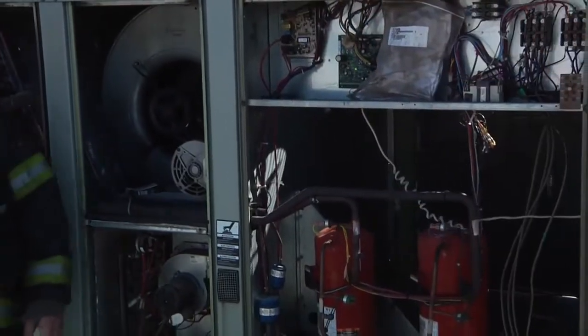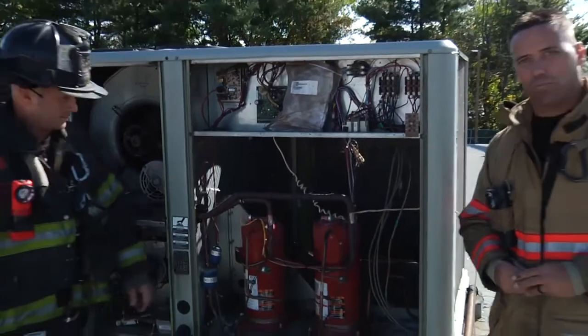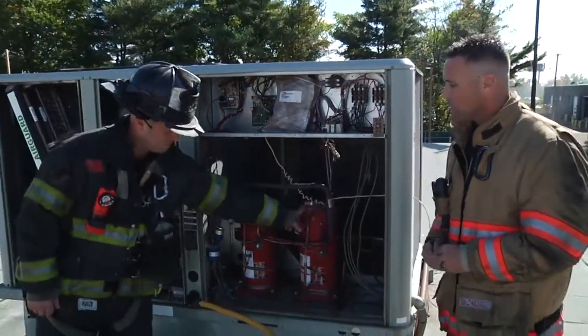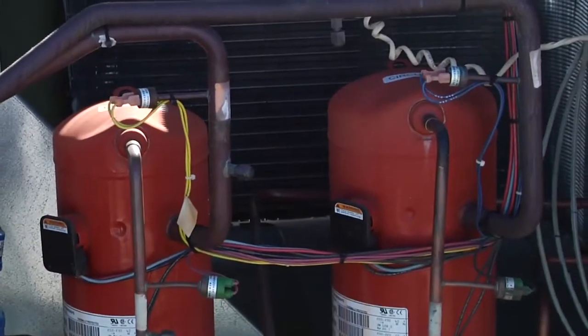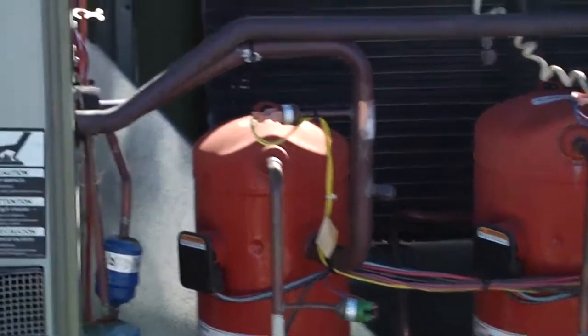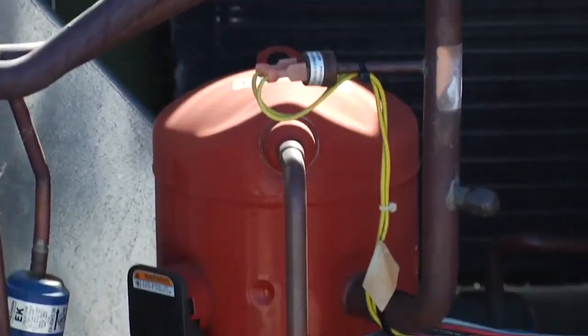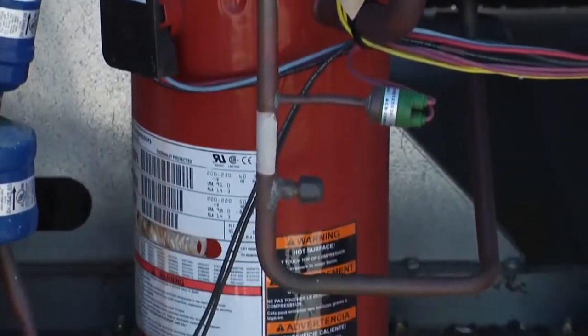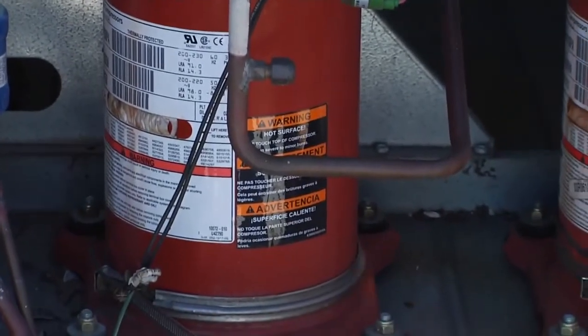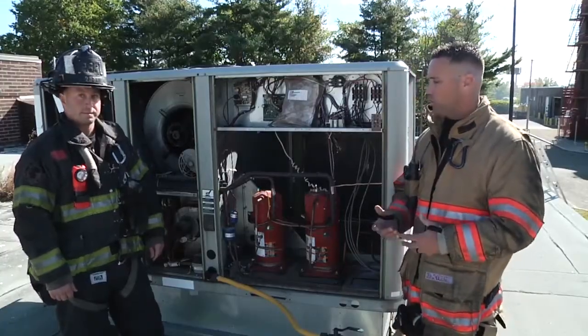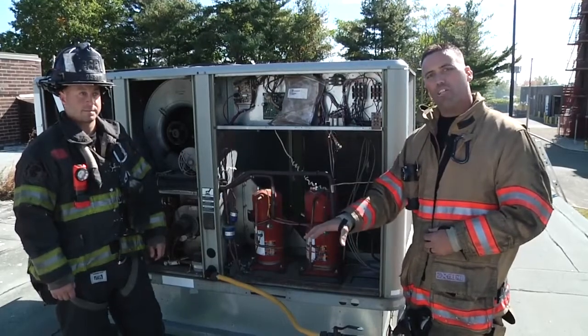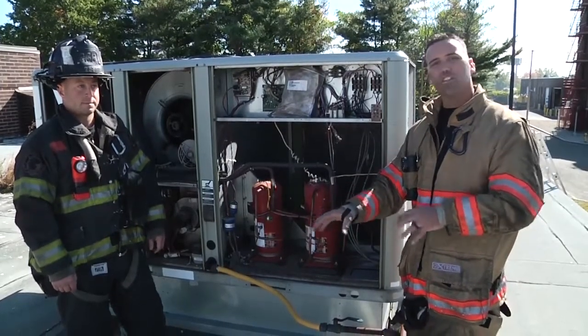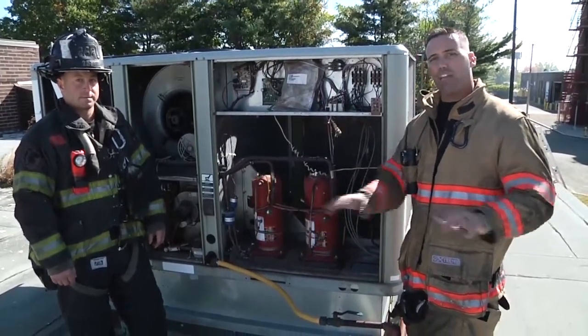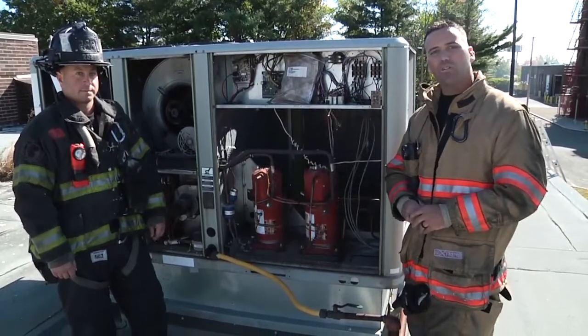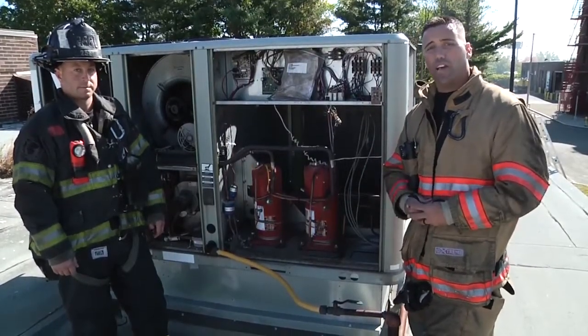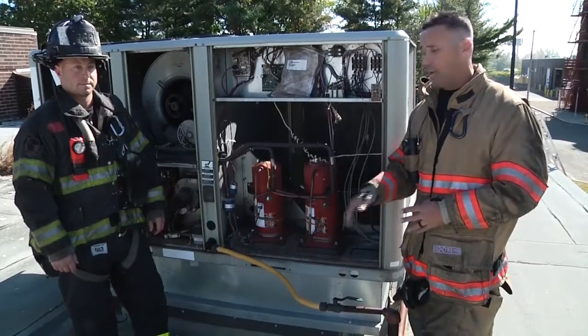Moving on, we have the compressors. This has been referred to as the heart of the cooling function of an RTU or an HVAC system. It is responsible for the entire heat transfer cycle. It takes the refrigerant from a low vapor pressure and transfers it to a high vapor pressure and back and forth. And this is really what allows the cooling portion of the HVAC system to work properly. Without it, it's not going to happen.